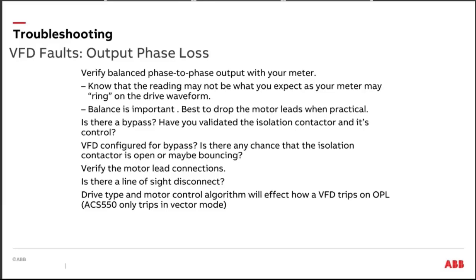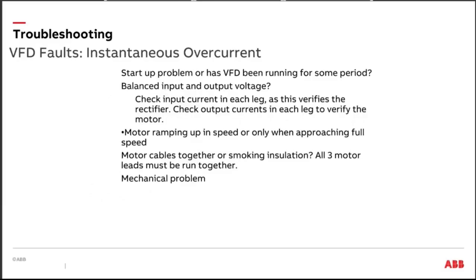If you're going to check your output, you might need to put the drive in vector mode and turn your output phase loss to no, so that the drive will operate with no load on it. That's common too. When I think about an instantaneous overcurrent trip, I like to think about how long the drive has been running. Is it startup, or has it been running for a long time? Quite naturally, I'm going to look at the output voltage from the drive to make sure I've got a nice balanced output. And I'm going to think about whether this is happening at a certain speed. Did something happen? Is it conditional? Is it on a conveyance system? We've got an end loader that's dropping rock or coal or something and impacting this conveyor belt, which has happened many times through my life when people have just dumped stuff on the conveyor belt and actually caused an instantaneous overcurrent on a conveyor belt.